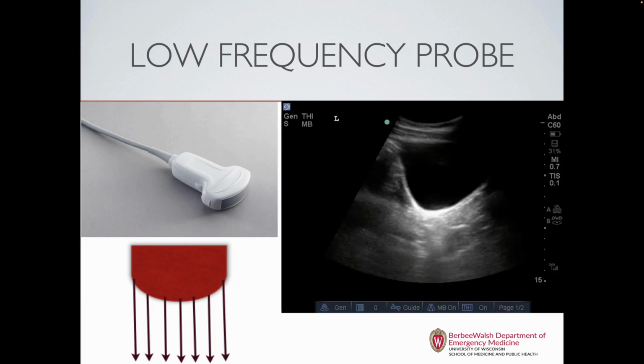The curvilinear probe is the next one that you've probably seen, and this is the one that we probably use the most often. It's the most utilitarian probe in the emergency department. This is the one that we use for the FAST exams that we do during trauma. It has the lowest frequency of vibration at 2 megahertz, but because of that, it's able to penetrate deeper. It'll go to a depth of about 30 centimeters. The resolution is not as good as the high frequency probe, and that's because of, again, the trade-off of depth for quality. The schematic here shows how that ultrasound beam shoots out straight into the tissue. The beams are equally spaced out from the curved footprint, but then it's able to collect them back on a curved shape.